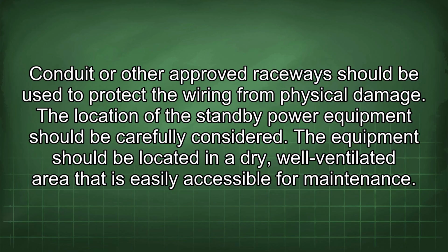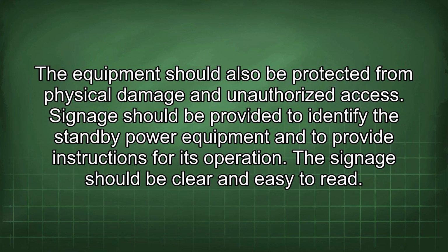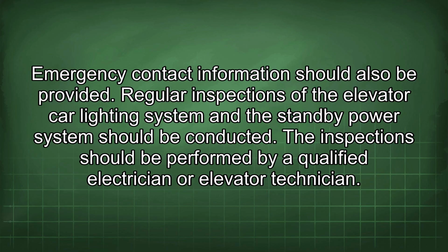The location of the standby power equipment should be carefully considered. The equipment should be located in a dry, well-ventilated area that is easily accessible for maintenance. The equipment should also be protected from physical damage and unauthorized access. Signage should be provided to identify the standby power equipment and to provide instructions for its operation. The signage should be clear and easy to read. Emergency contact information should also be provided.